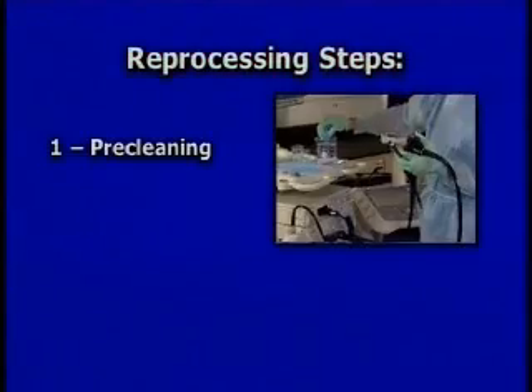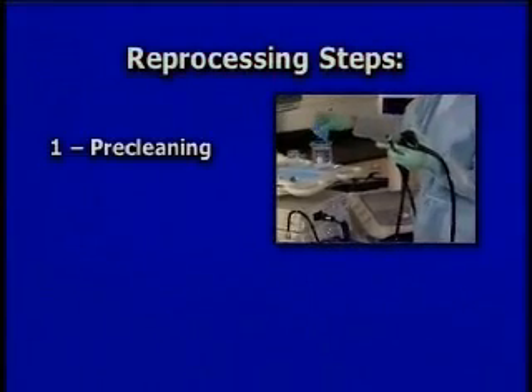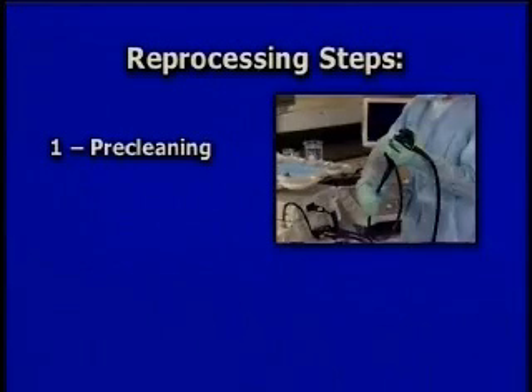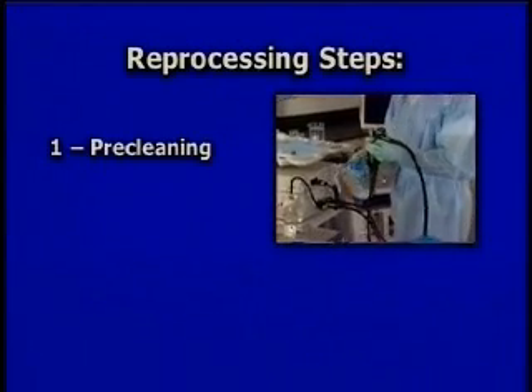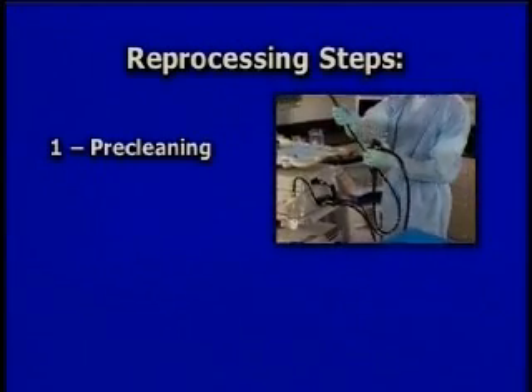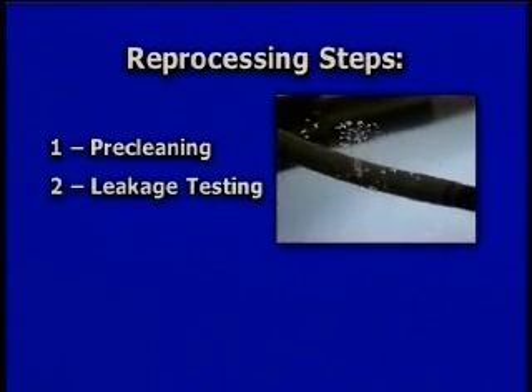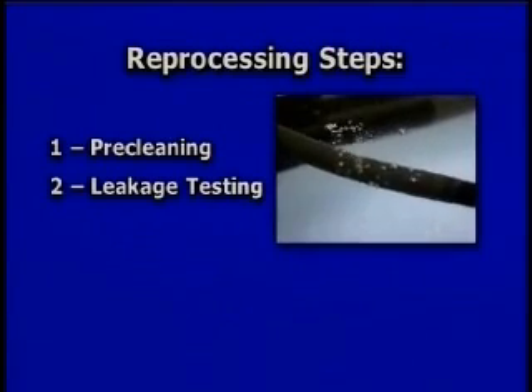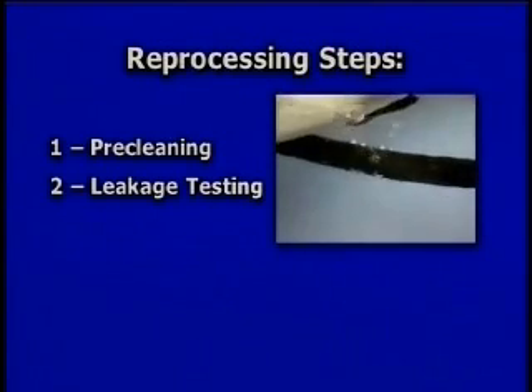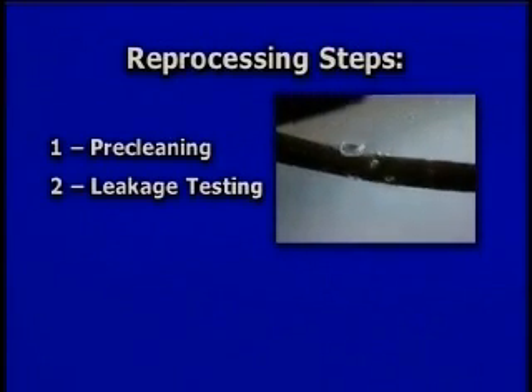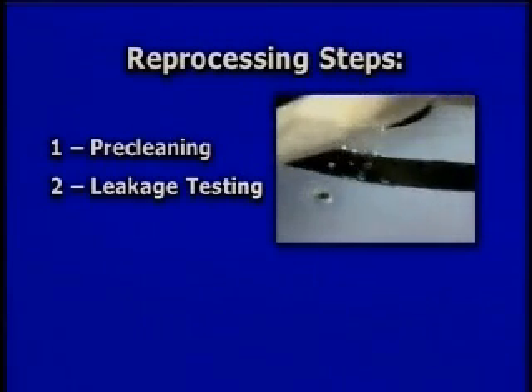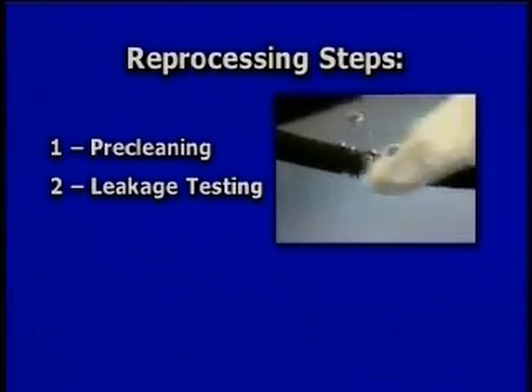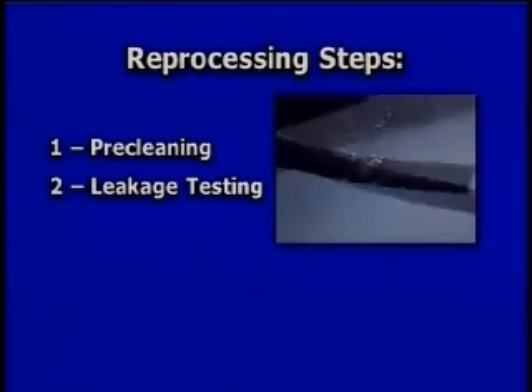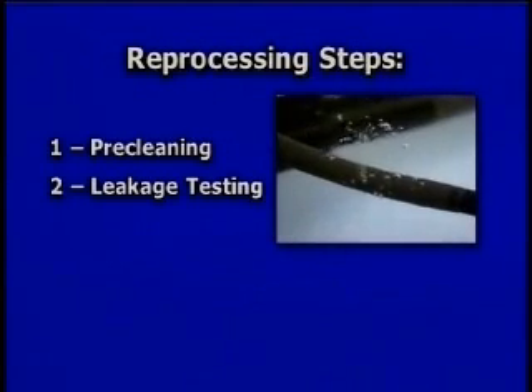There are 4 steps immediately after the patient procedure. Pre-cleaning removes gross debris and prevents patient material from drying onto the endoscope. The second step is leakage testing. Leakage testing ensures that the endoscope is air and fluid tight. A leaking endoscope will be severely damaged if fluids enter the instrument. Leaking endoscopes also present an infection control risk.